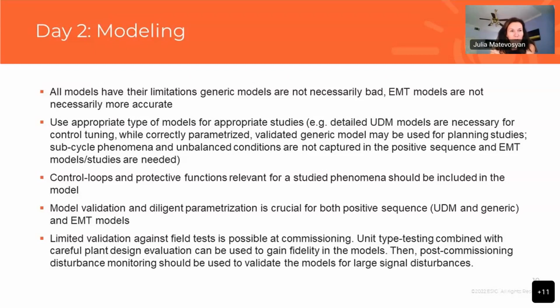And I think today Steven talked to that as well. So what may have happened in the Odessa event disturbance that was not reflected in the models, even EMT models. Model validation and diligent parameterization is crucial for any type of model. Limited validation is possible before and at commissioning, so unit type testing should be used for that, combined with careful plant design evaluation, and this can be used to gain fidelity in the models. And then post-commissioning disturbance monitoring can be used to provide more information and validate models for large signal disturbances as they happen.